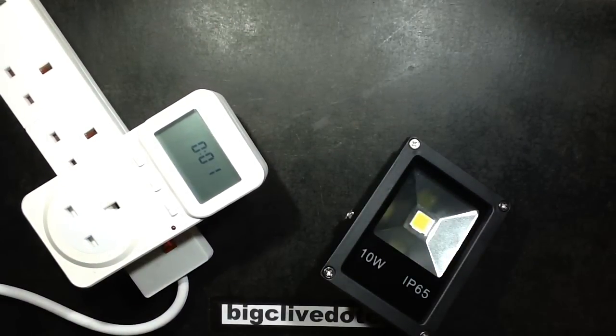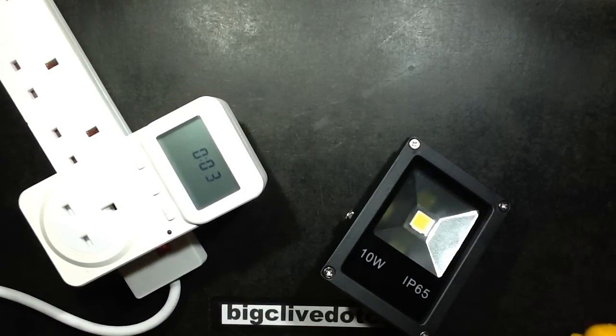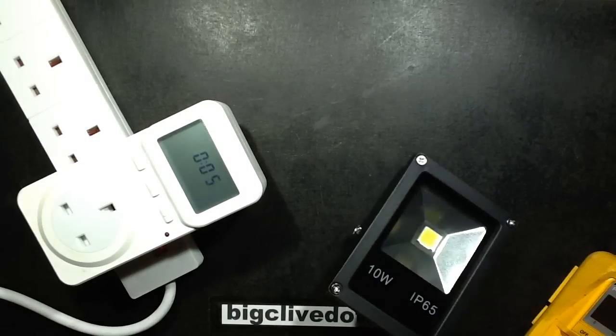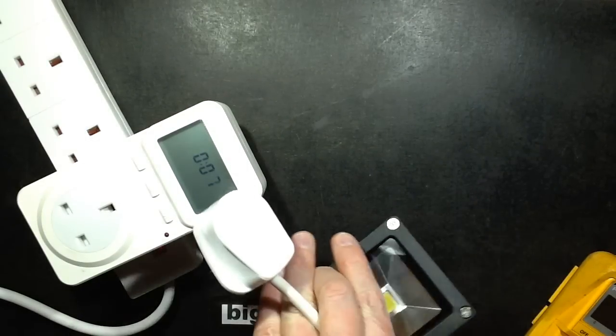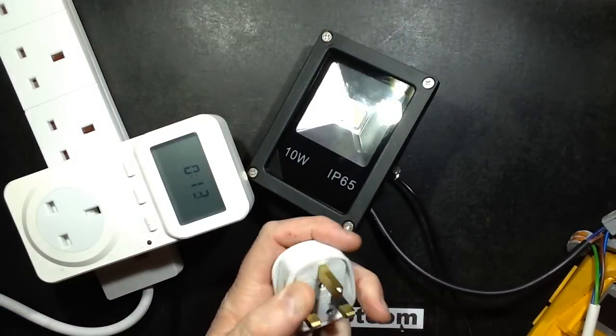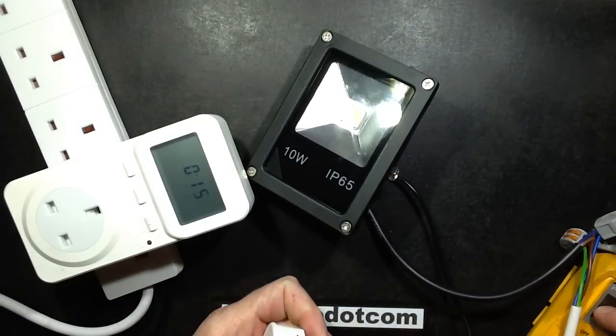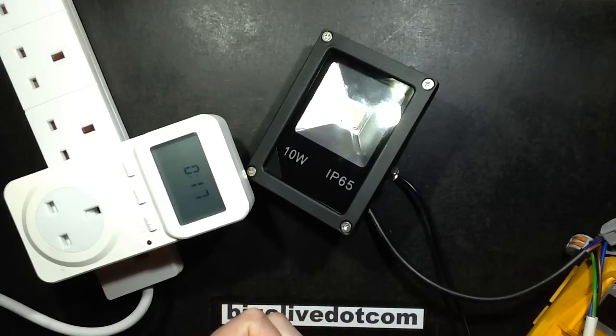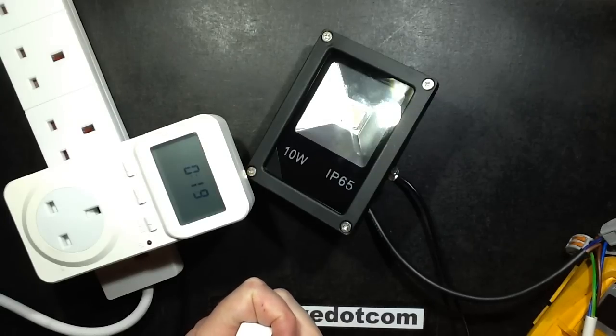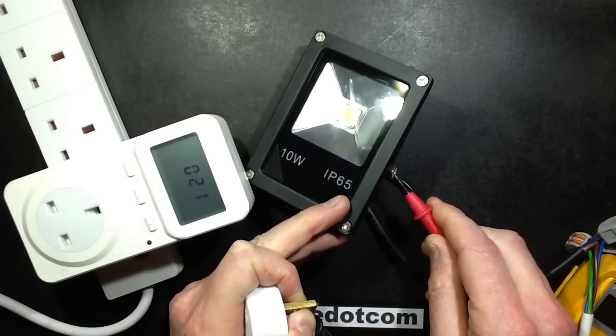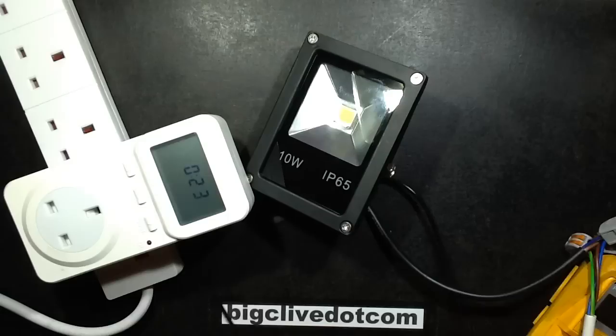We'll do the earth test. It's got a modestly short lead - slightly longer than many others. So we'll test from the earth pin onto the case and it's earthed. That's a good start.